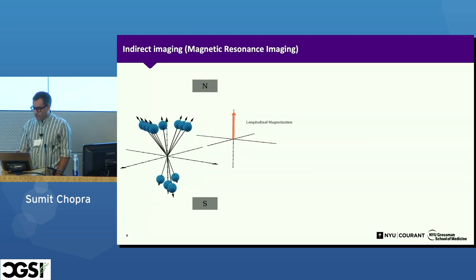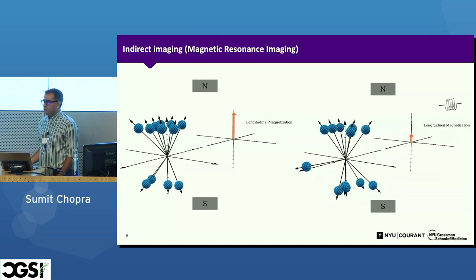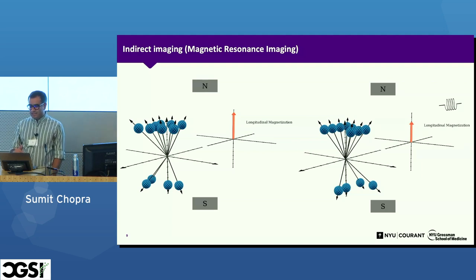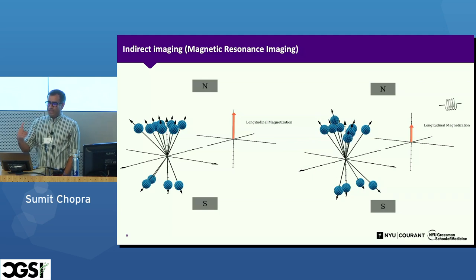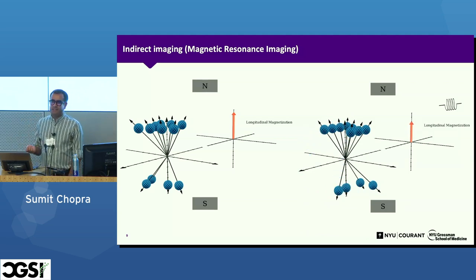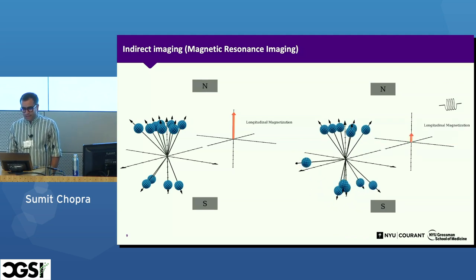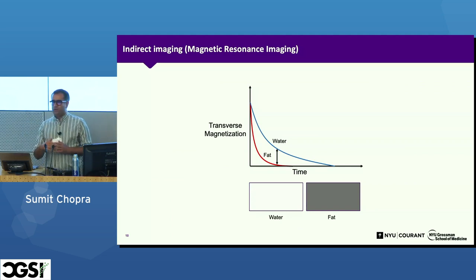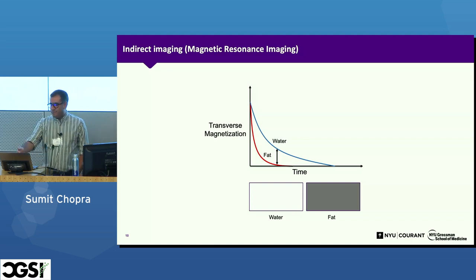When you stop the radio frequency pulse, the reverse happens: the protons dephase and go back to their low energy state, the transverse magnetization decreases, and the longitudinal magnetization goes back up. When you place an electric coil near these changing magnetizations, as physics 101 would say, an electric current is generated — and it's that current that gets measured as the signal by the machine. Notably, protons from different tissues take different amounts of time to return to their natural state. For water it takes longer; for fat, much faster. This difference in time gets translated into different shades of gray on the actual image.